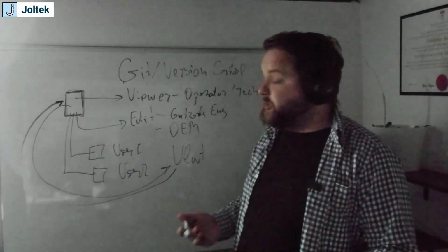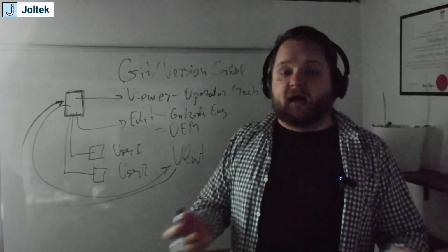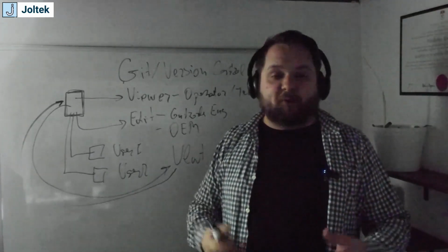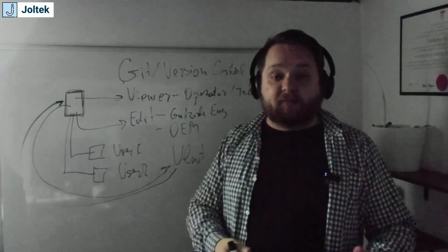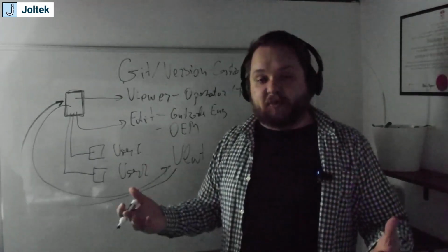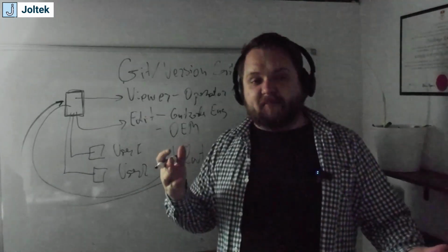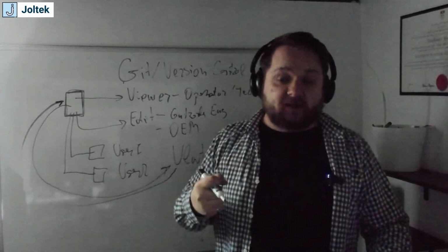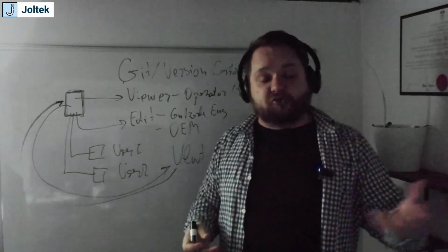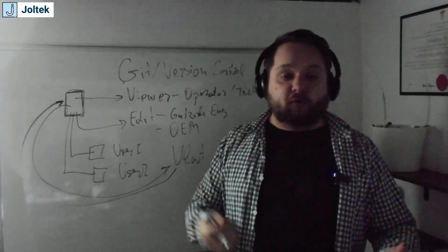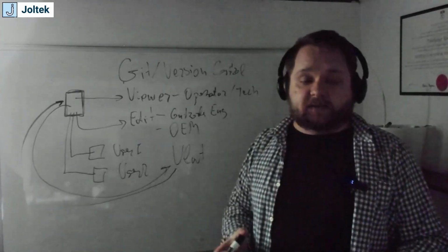So that is also a huge opportunity, because a lot of times when I go to different facilities, I would ask who's got the software. And someone on third shift inevitably has a laptop with all the files, all the PLC programs, all the HMI programs that has made a bunch of changes, or other people have made changes. They pulled it from the PLC, some of them pulled it from a drive that was old. So now there's no single source of truth for those files. So the opportunity is really big.